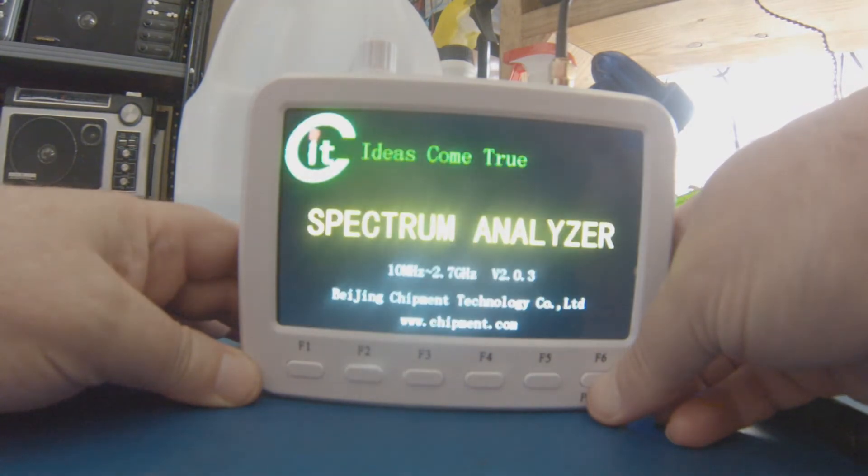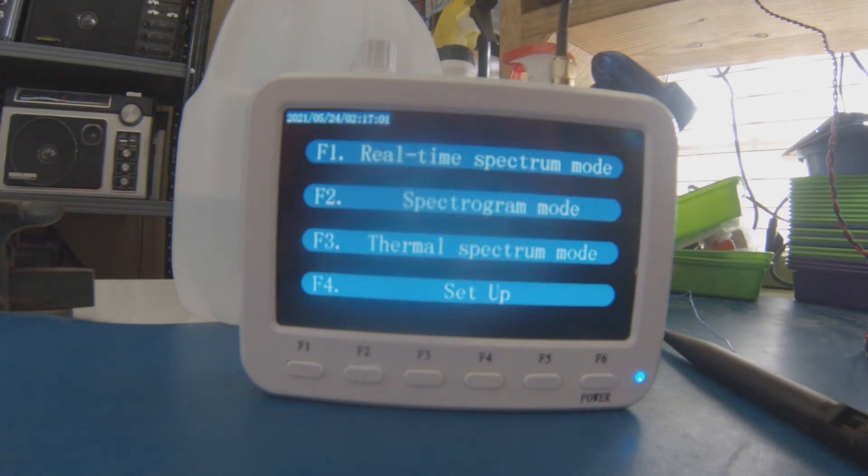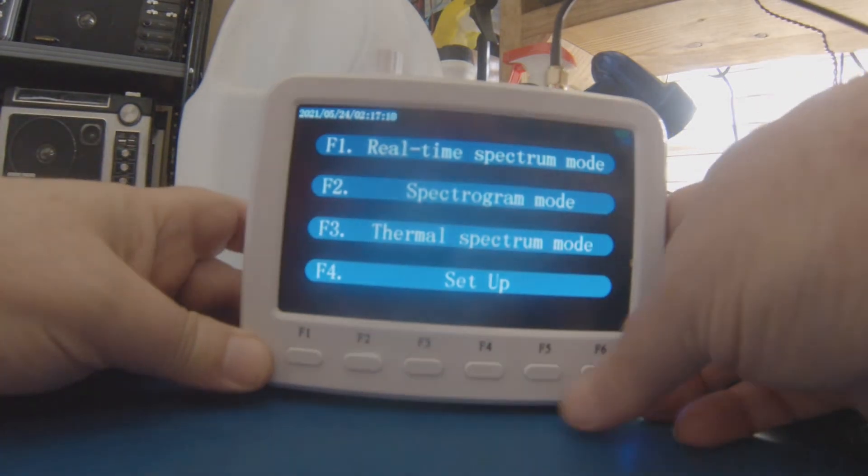To turn it on, you activate the right-hand soft key which is also labeled power, and there you have the frequency range. It comes up with a menu: real-time spectrum analyzer, spectrogram, thermal spectrum, setup. We'll look at the setup first.